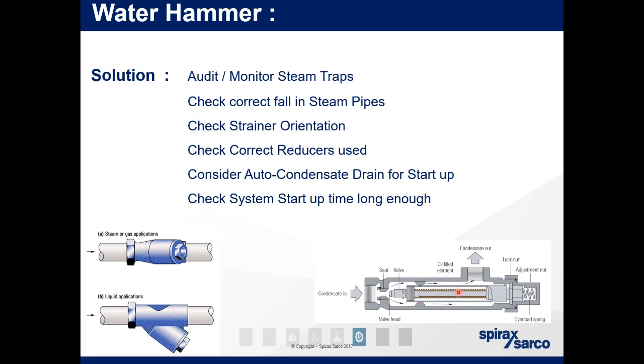Yeah, so it's damaging. Say you have a float trap and you introduce water hammer there. The float trap works by a ball that floats on top of the condensate. As the condensate rises, so does the ball. That opens the trap and allows for the clearance of that condensate. If you have water hammer, so the Mach speed that's in there, you effectively hit that ball with energy, which is the water in this case, which is non-compressible. So it's like taking a hammer to that ball. Over time and with enough speed, enough energy, you'll collapse the ball. So it will sink in that trap and it will fail closed.